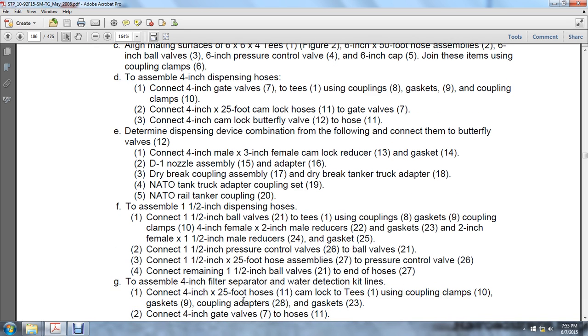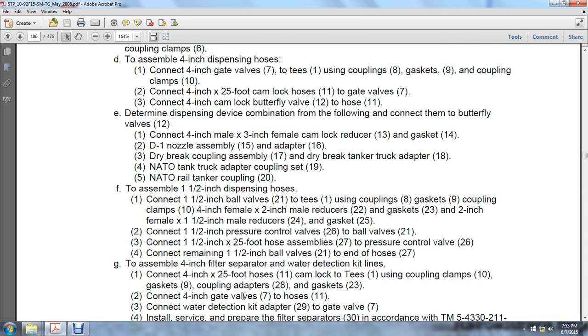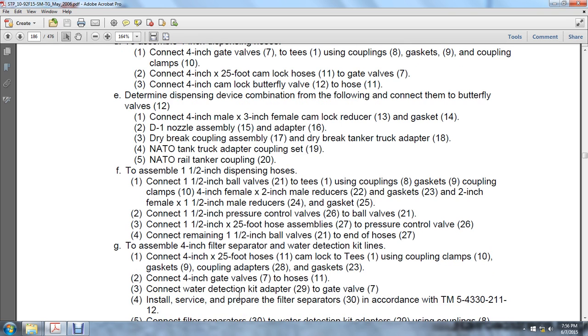To assemble the 4-inch filter separator, water detection kit, and lines: connect the 4-inch 25-foot cam lock hose to the tees using coupling clamps (10), gasket, coupling adapters, and gaskets. Connect the 4-inch gate valves (7) and hoses (11). Connect the water detection kit adapter (29) to the gate valve.